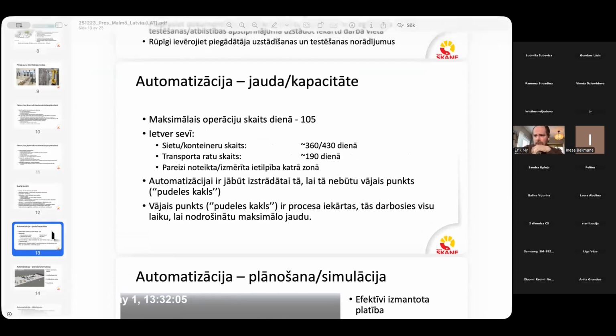If we go to capacity, our sterile central is supposed to be able to supply materials to 105 operations per day, or surgical procedures. And that, in our case at least, translates into around 360 to 430 baskets, containers each day. And they are loaded into 190 trolleys, case carts a day. These are the overall capacity demands, but those can then be broken down to a capacity needed for each zone. If you have 4 autoclaves, each autoclave needs to be able to do a quarter of this, at least, maybe a third, so that you can have one autoclave out of order and still make the capacity.